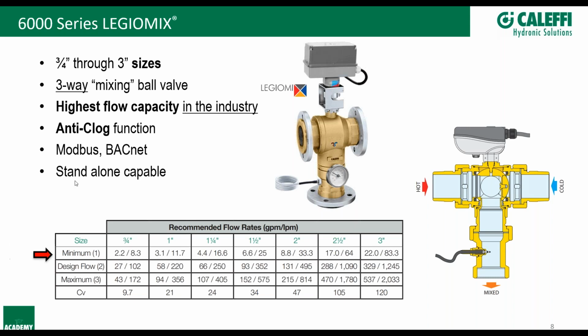But one other cool thing that we have to help out those people with the really harsh water conditions is a function called anti-clog. Anti-clog is basically a work of art here between the control and the valve and the actuator here. And what it does is it actually will do a full stroke of the ball inside the valve assembly in both directions. It'll do a stroke in both directions once a day. So if you do have any debris or scaling on that ball, it's going to clean it off. And I think that's really great. And obviously, if you even look at this 3-way ball valve assembly, there's next to nothing inside of here. So the idea of scaling and debris and catching a bunch of junk in there, it's going to be at pretty much a minimum anyways, but the anti-clog function will make it that much better. So really great valve for harsh water conditions.